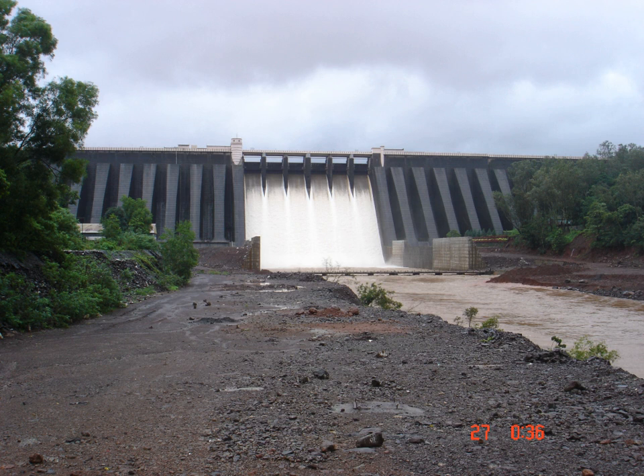Each of the two stages has four turbines with a capacity of 65 MW each for the first stage and 75 MW each for the second stage. The water from Shivasagar Reservoir is taken through an intake structure known as Nava Tower near the village of Nava into the Head Race Tunnel, then travels towards the surge tank. It is further divided into four pressure shafts which run vertically downward delivering water to the turbines, and the water is then discharged into the tail race tunnel. A dam foot powerhouse was also constructed, which generates electricity using water discharged from the Koyna Dam for irrigation purposes. It has two Francis turbine units of 20 MW each, run according to the irrigation requirements of the downstream areas. The combined installed capacity of the two stages and the dam foot powerhouse is 600 MW.